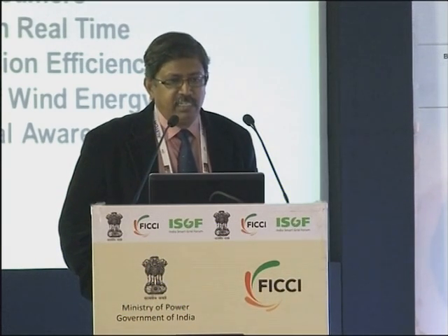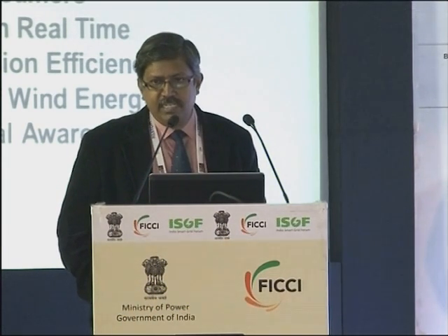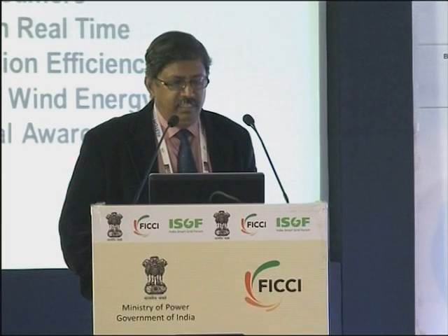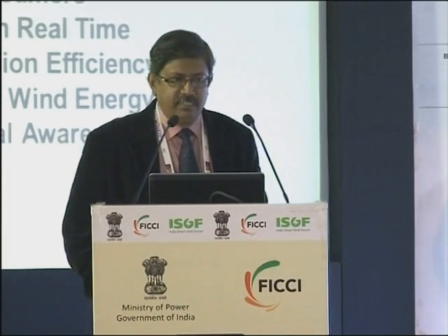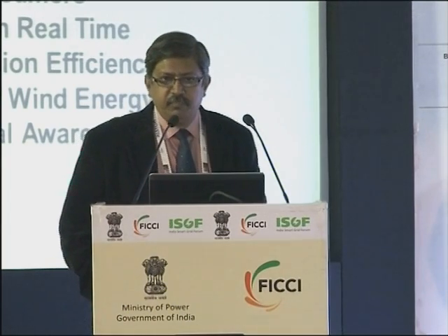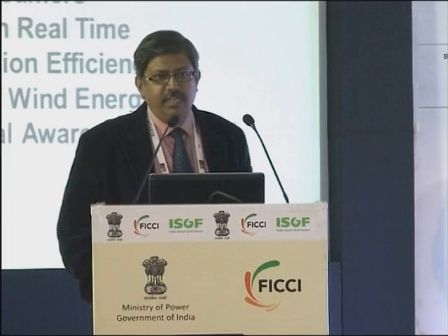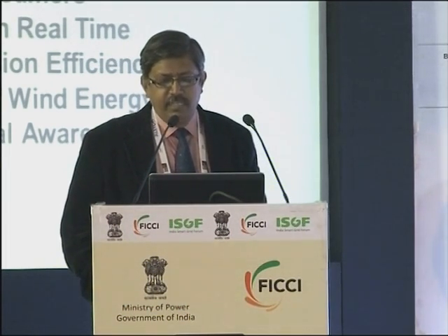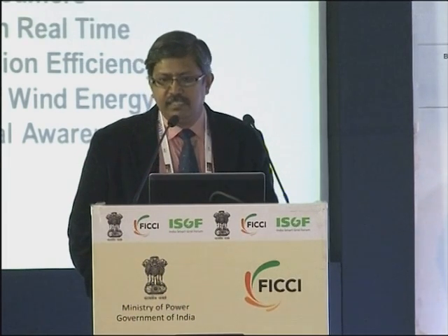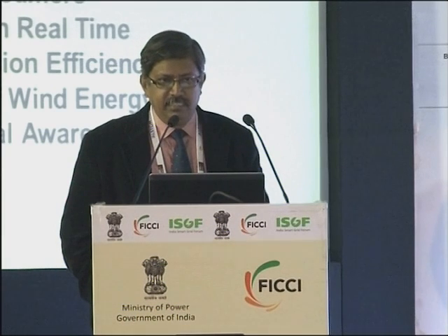The benefits of DLR: it's cost effective because we are just putting in some extra technology, sensors and equipment. It is congestion relief, so it gives you good relief for short time congestions. It cannot address long-term congestions. Improved grid reliability: as we saw in the earlier sketch, if we could allow the line rating to be increased for very short terms, and today there are even relays with DLR settings.